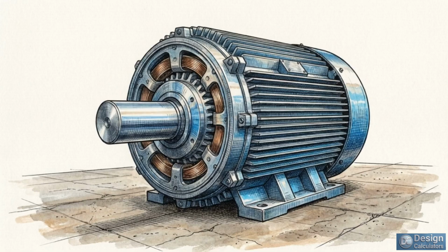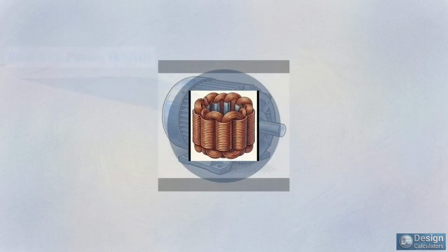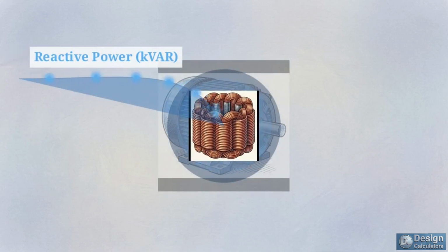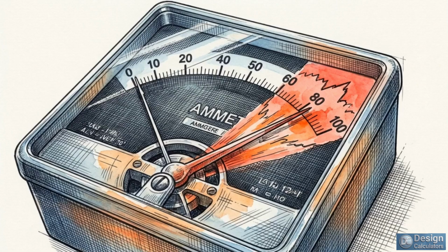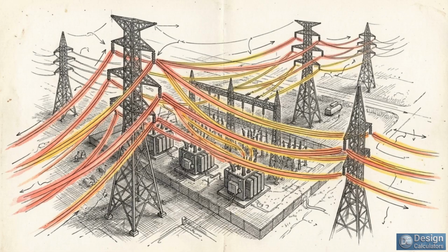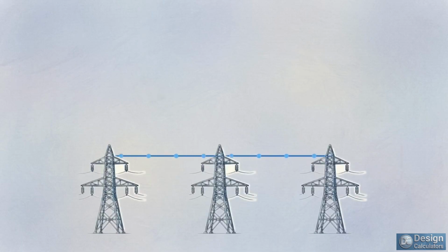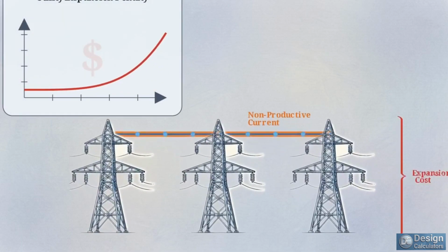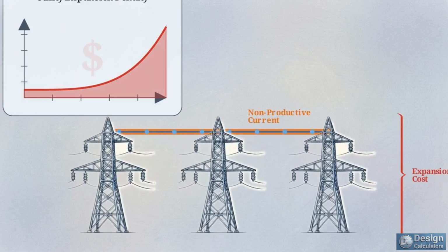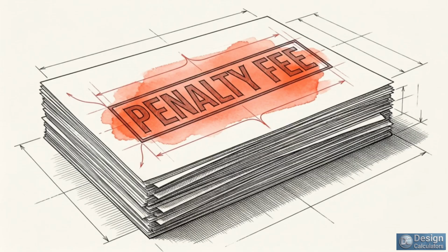However, heavy industry relies almost entirely on AC induction motors. To operate, these machines draw on a hidden electrical requirement that must be actively managed by the facility. When an industrial plant ignores this hidden requirement, the induction motors pull extra current, forcing the entire local electrical grid to choke under unnecessary load. Because utilities have to build larger infrastructure to supply that extra, non-productive current, they charge for it. Global industries pay millions in penalties for electricity that performs zero physical work.